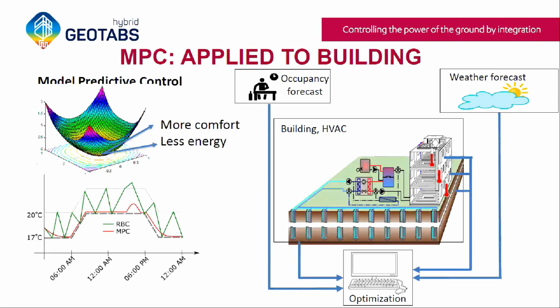We also need an occupancy forecast, firstly to know when people will be in the building, so when it needs to be warm. But also, because in modern buildings internal gains are a major source of heat, you may actually need to cool the building down. If you put all this information into the optimization algorithm, you get a multidimensional curve - here shown in two dimensions - where there's probably one point that uses the least energy while still providing all the required comfort.